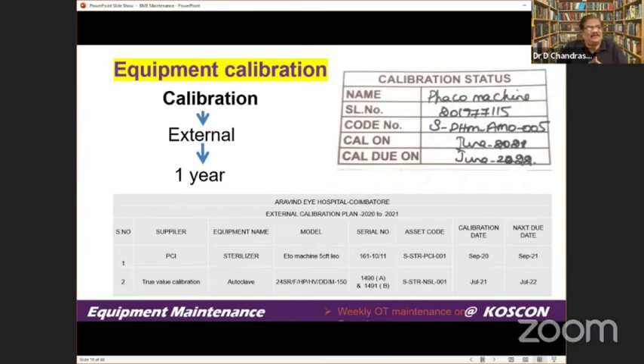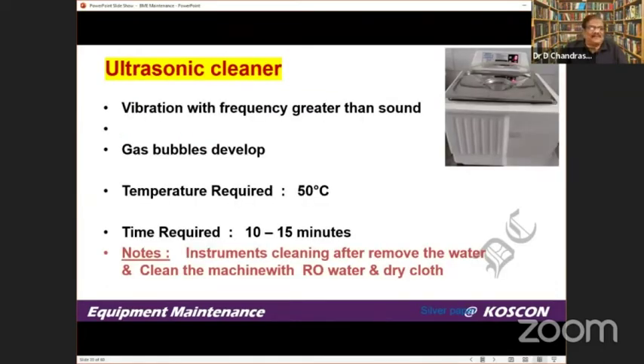Calibration is very important. Make sure it is done at least once a year, always by a third party authorized to calibrate machines. We should know the parameters for calibration, as these are important. If there is a breakthrough or outbreak of infection, these records will give us a lot of legal value. For example, take the ultrasonic cleaner.